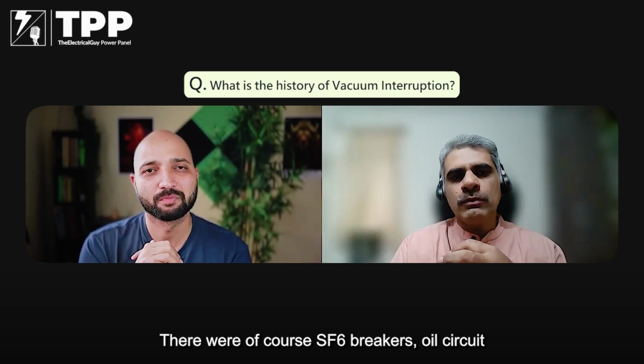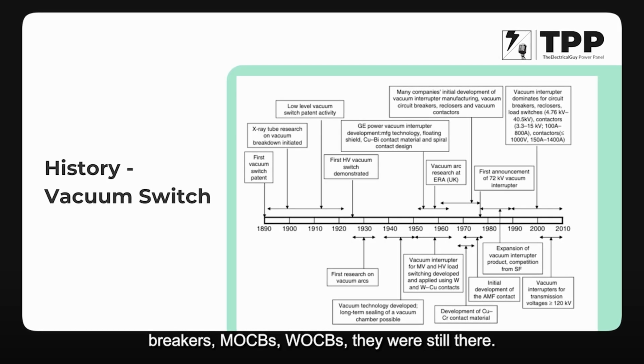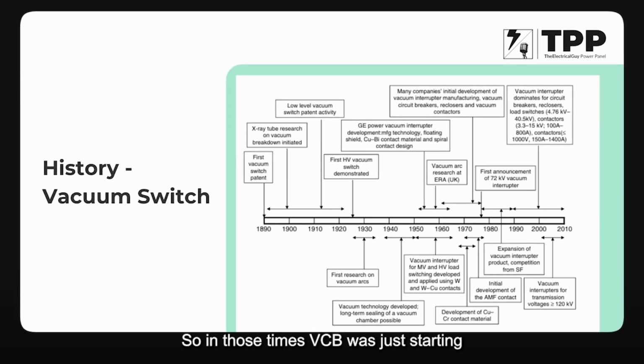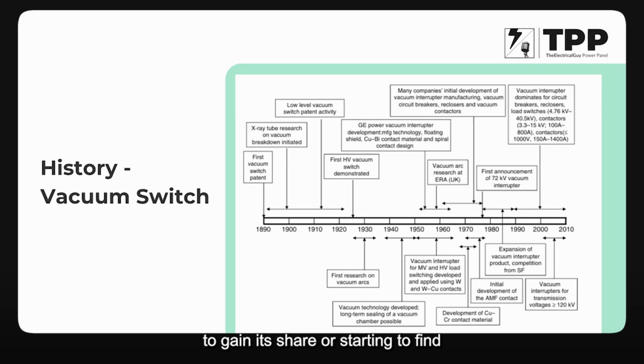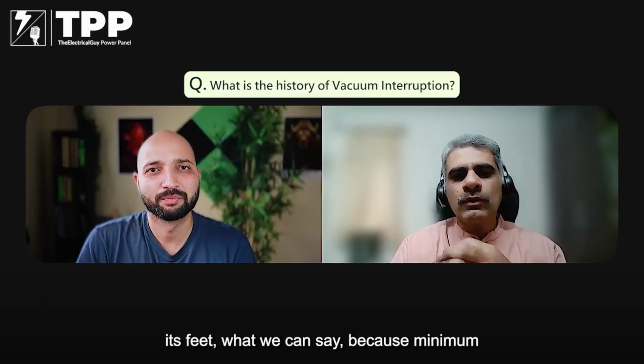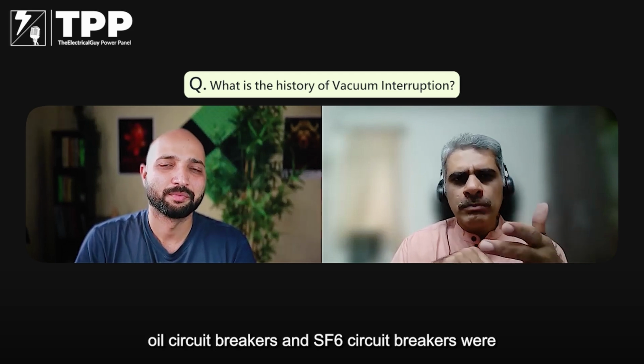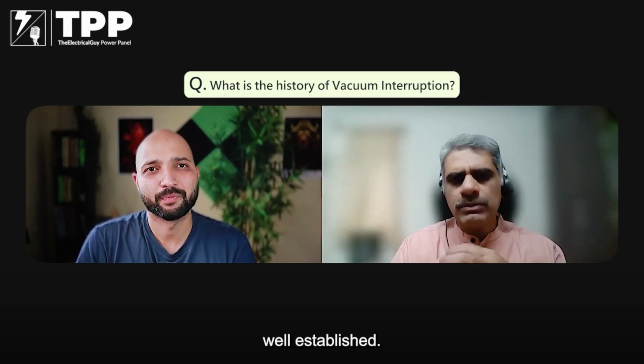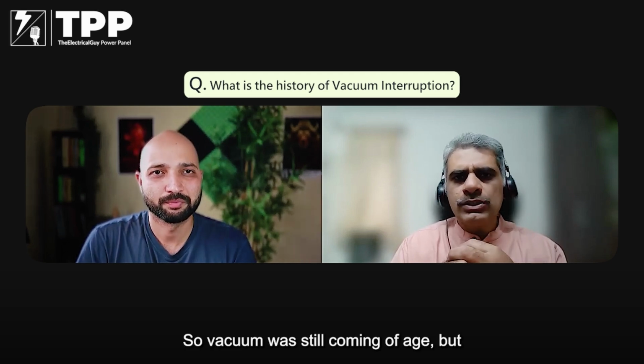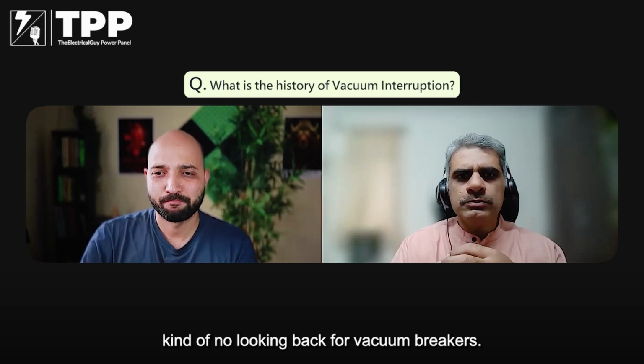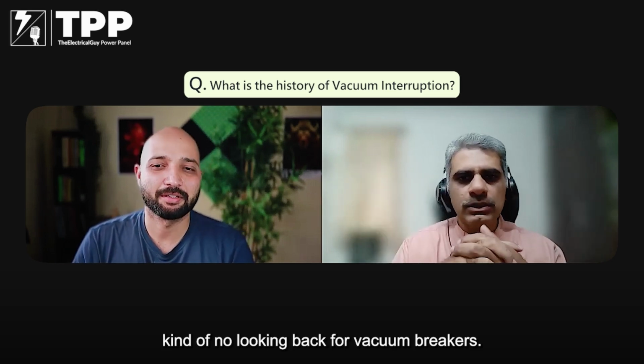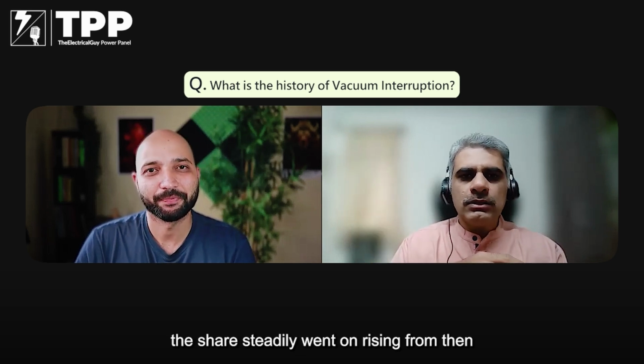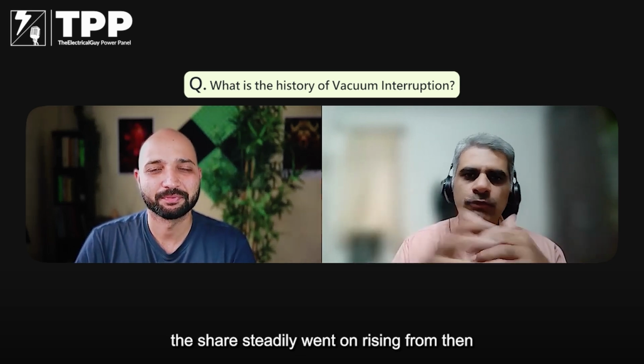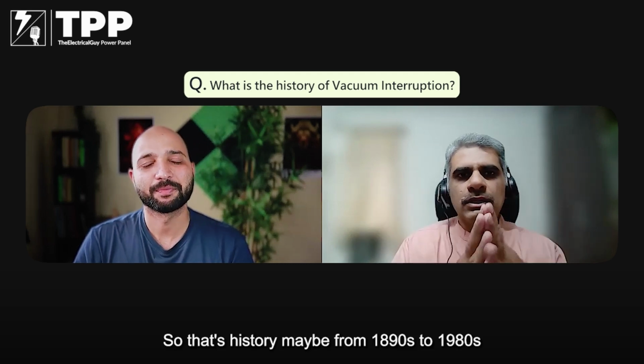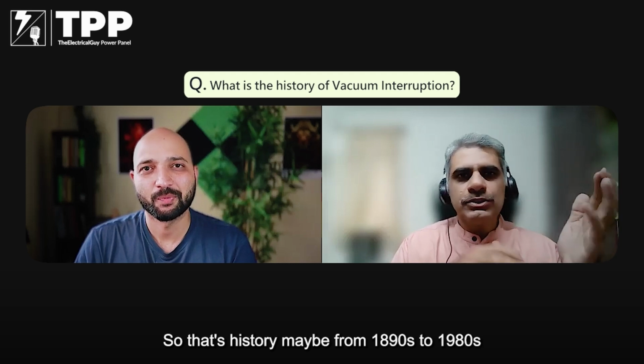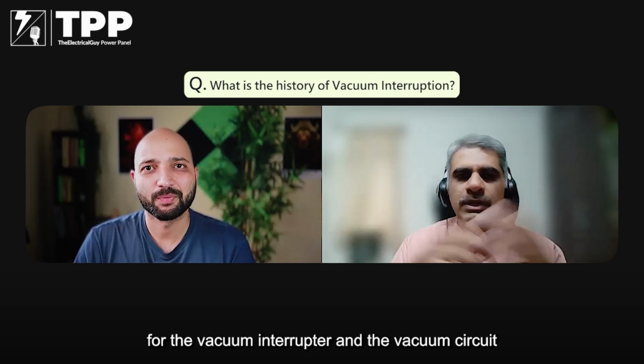There were, of course, SF6 breakers, oil circuit breakers, the MOCBs, the BOCBs, still there. So in those times, VCB was just starting to gain its share, starting to find its feet, because bulk oil, minimum oil circuit breakers and SF6 circuit breakers were well established. So vacuum was still coming of age. But then in the next 10 years, it was no looking back for vacuum breakers. It became a game changer, a product of choice, and then the share steadily went on rising from then onwards. So that's the history, from the 1890s to the 1980s, for the vacuum interrupter and the vacuum circuit breaker.